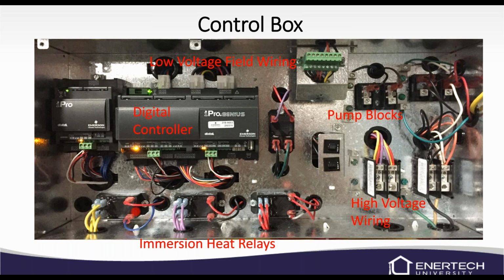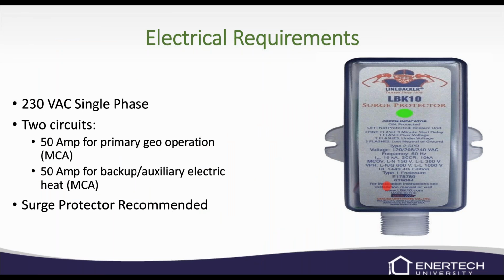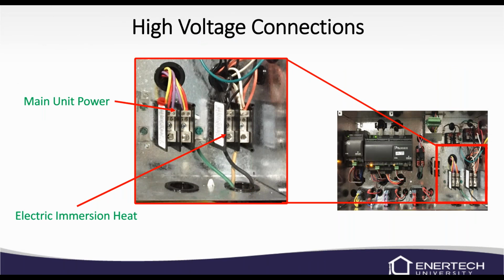These are your immersion heater relays, so it's staged, and it'll turn these on based on the parameters set up on your controller. We would recommend a surge protector on the unit. Remember that this is a 208, 230 volt single phase unit, and it will have two different circuits, one for your geo and one for your backup electric heat. High voltage connection, you got your main power. Actually, I think it's flip-flop. This might be your electric immersion, and this might be your main power. I can't really be honest remember, but there will be a sticker that'll tell you. So you don't have to remember either.